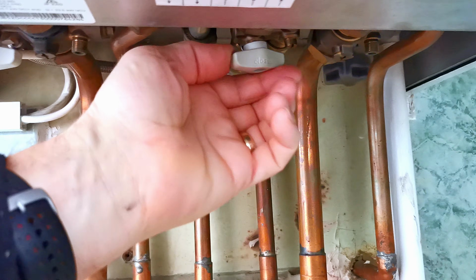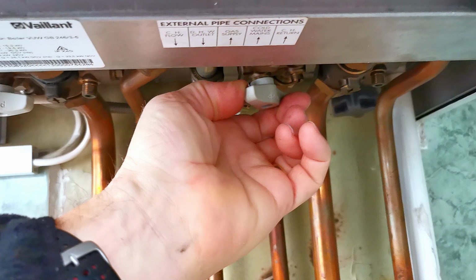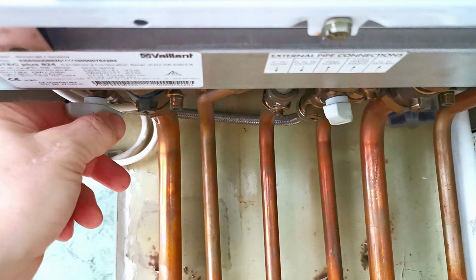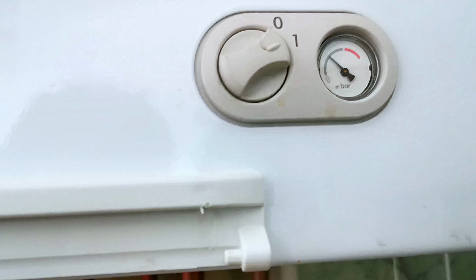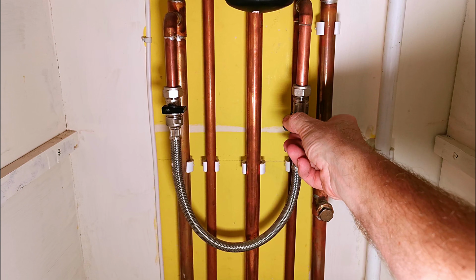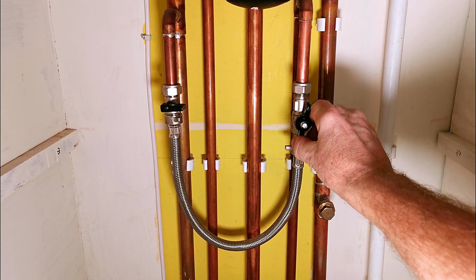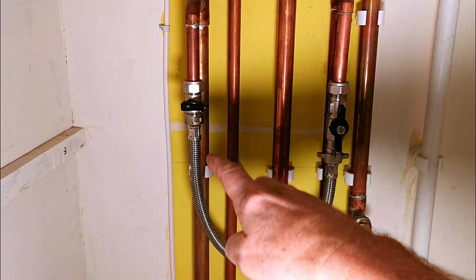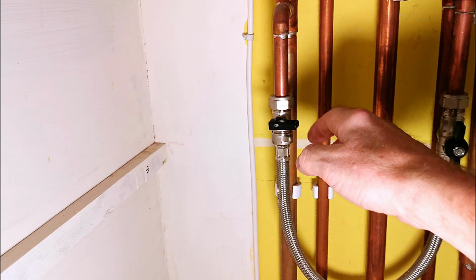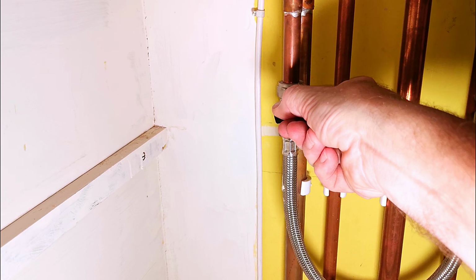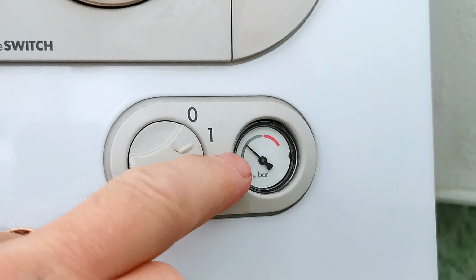Now it's just a case of topping up the boiler or system. On the Vaillant ecoTEC Plus boilers, we've got the two handles underneath. Just open both of these. If you've got a Vaillant Pro, you'll need to find a filling loop and top the boiler up from there. And we're looking to get about 1.5 bar. If you have a gauge on the front of your boiler, that's about the middle of the grey area.